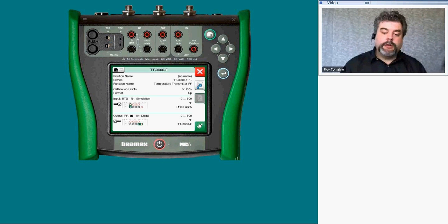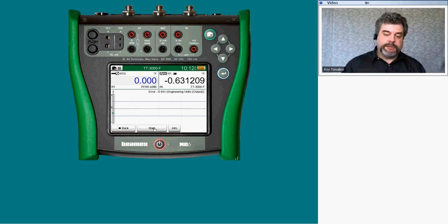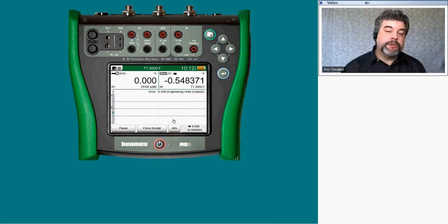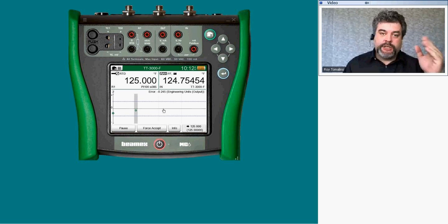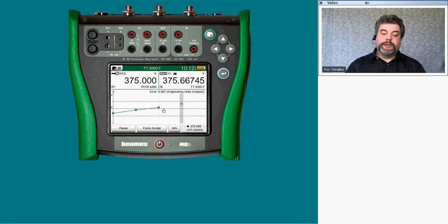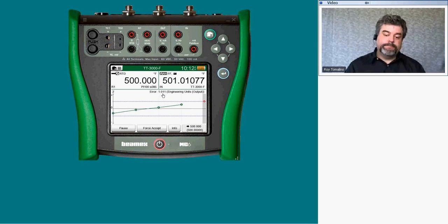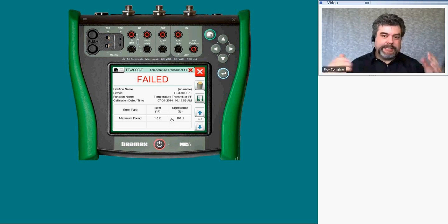Let me hit start. Our first test point is zero degrees in and zero degrees out. There is no 4 to 20 milliamp output on this — this is a purely digital signal. The zero would be perfect if we're sitting right on zero. The blue dotted lines is the tolerance. As long as our test points land within the blue lines, we know that it's a passing test point. Looking at the graph, we can see the actual error right above the graph — we have about a 0.6 degree error. And it looks like my last test point actually failed.